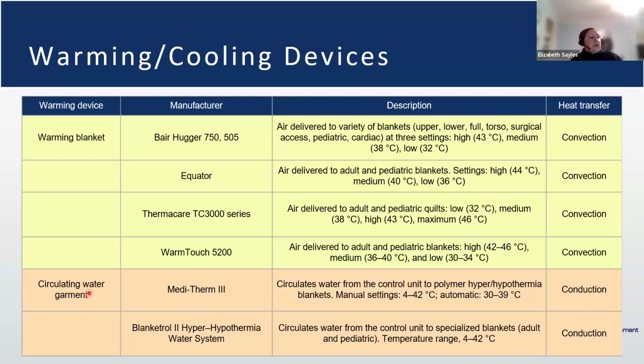In terms of the circulating water garment conduction device, one that's not listed here that we actually have, and I talked about the 14-day disinfection requirement, is the Stryker Altrix. We were one of the first organizations to implement that device right as it was approved by the FDA. And we found a lot of issues in terms of how to maintain those devices, in the sense that the design of those devices is horrible.